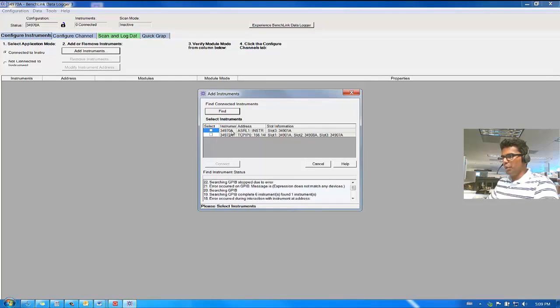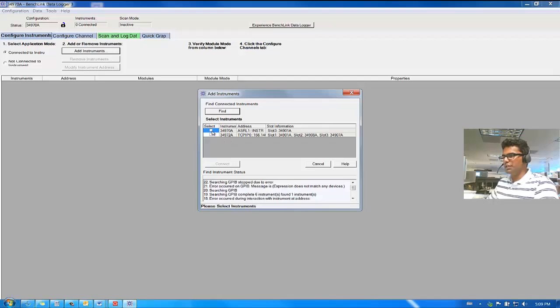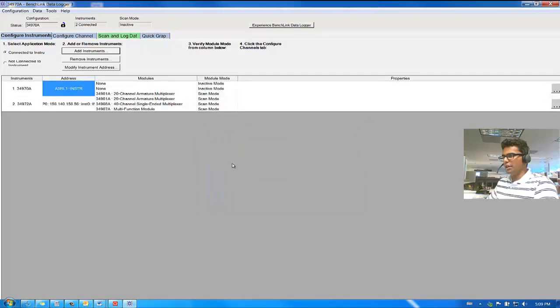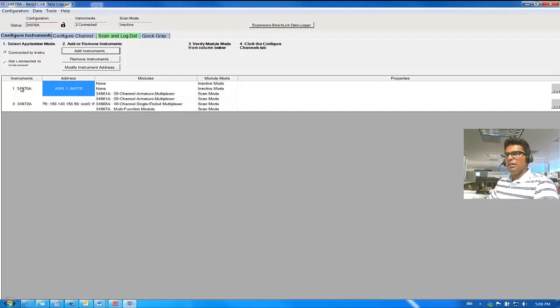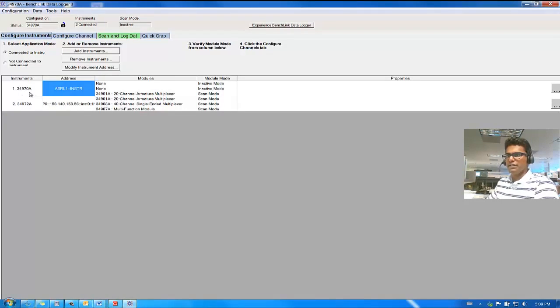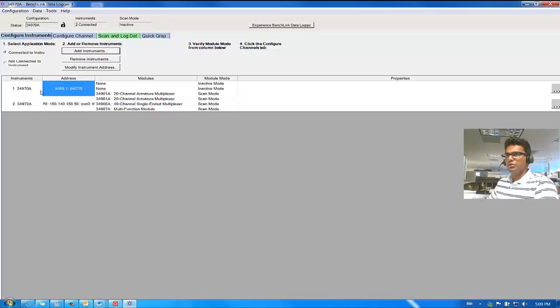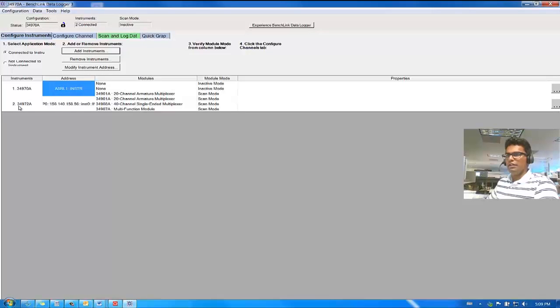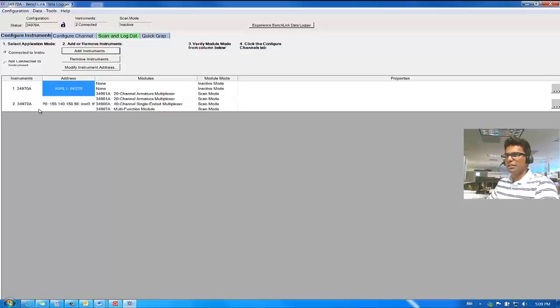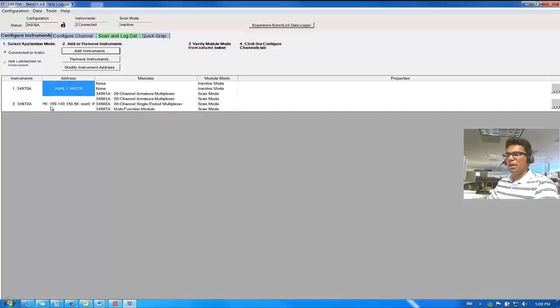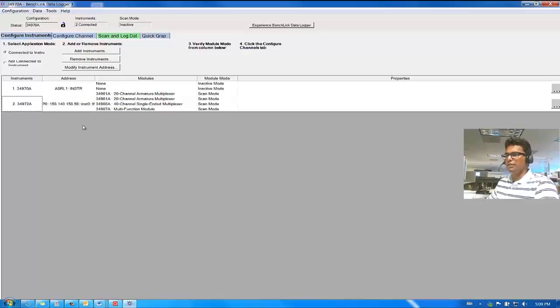Now, we have both instruments available to us. Select on both of them and click on Connect. And there you go. Now you have the 34970A connected through RS-232 to your Benchlink Data Logger Software, and the 34972A connected to your Benchlink Data Logger Software through LAN interface. And it's the same IP address.